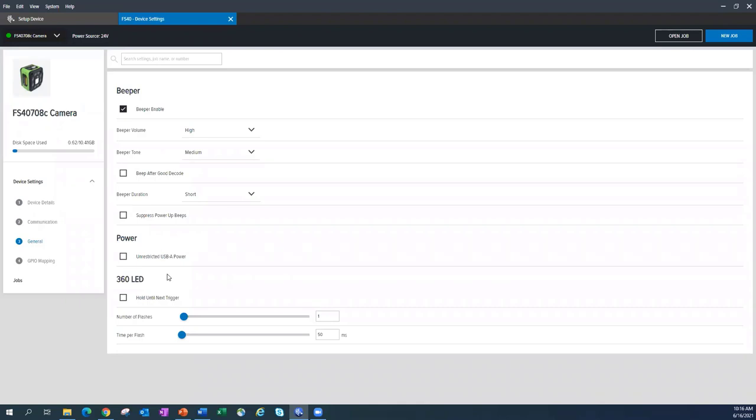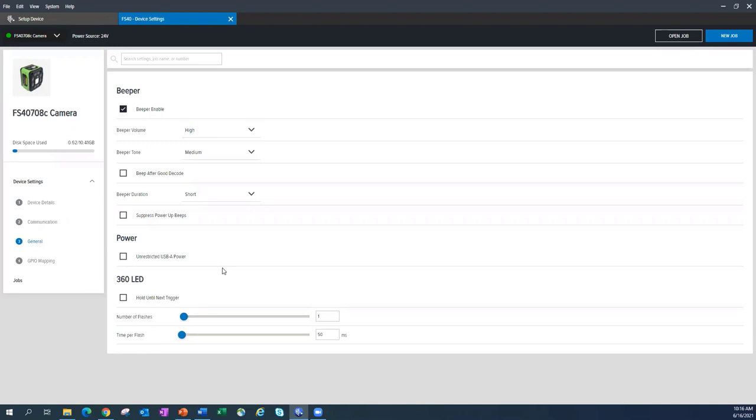Next item down is the 360 LED. This is the indicator that's on every side of the 40 as well as the 70. So when you get a good decode or pass a vision system, this is where you could flash it green or flash it red. This allows you to change the behavior of it. So when a barcode reads, you can hold it until the next trigger such that you know that the device read the last time. You can also specify how many flashes you want, how much time per flash or the frequency of the flash. You could do that as well. So all that is adjustable here in that general settings tab. Now keep in mind that this is the software and these screens I'm showing you are common between both FS and VS. So whether you're doing machine vision or barcode reading, all of these settings you see here are identical and will look the same.